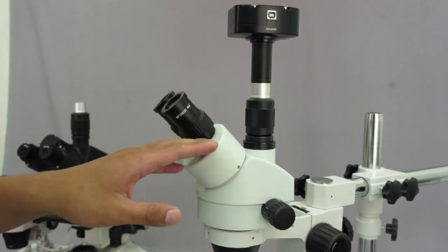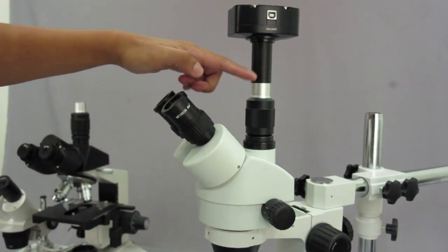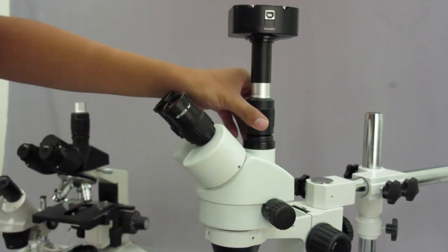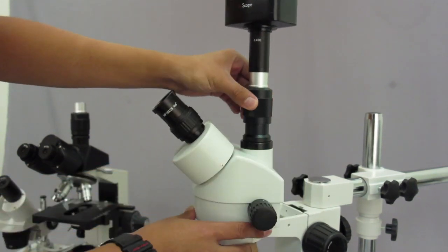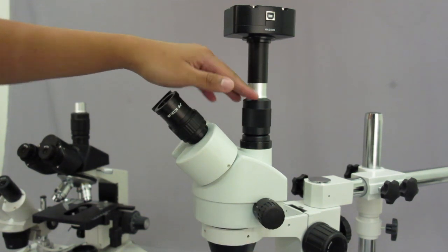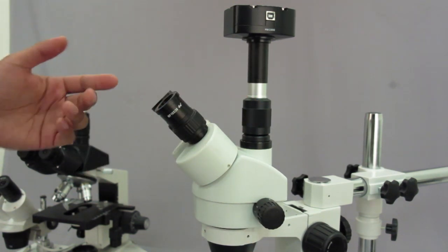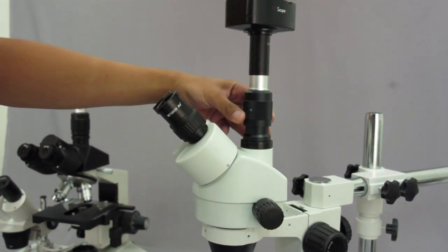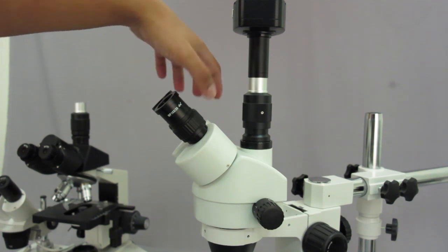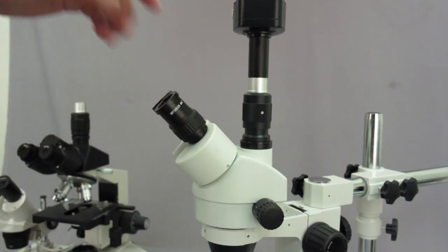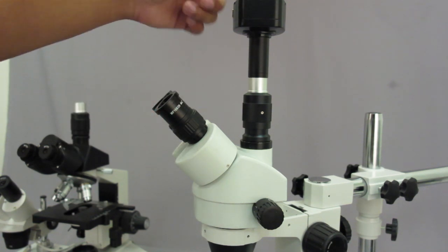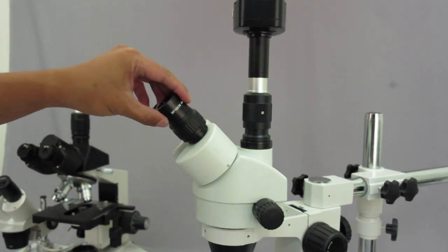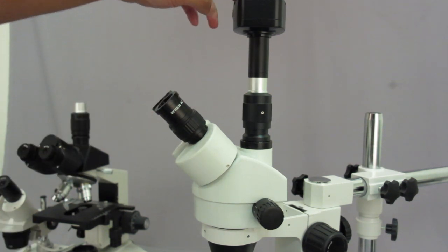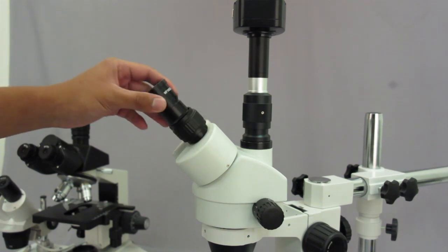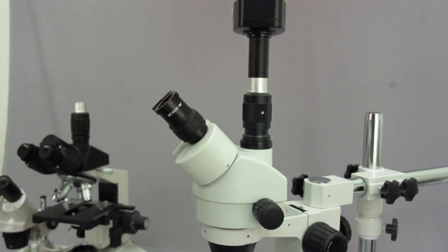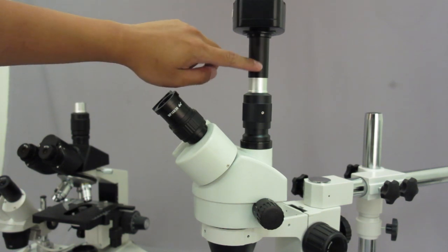Now, if you want to match the focal distance of the microscope and the camera, you could always readjust the trinocular port. So you can move it up, or you can move it down. And all you have to do is twist the trinocular port. A lot of people don't know that you could readjust focus when using this port alone. Doing this would allow you to match the same focusing ability that your eyepieces get, especially if you have 20x eyepieces in it. Some people always say, hey, my magnification of the camera doesn't match the magnification of the eyepieces. And that's technically true because the magnification of the camera is a little bit more if you have 10x eyepieces in it. So expect to see a somewhat smaller field of view when you connect the camera to it, even with the reduction lens attached.